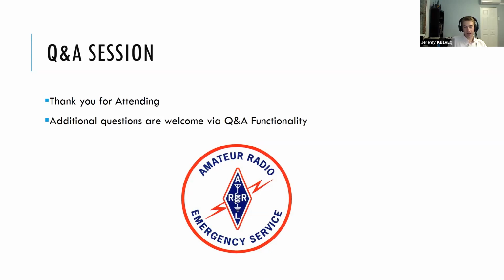It's one of those things, and it's obvious I'm an engineer when I say it, right? But efficiency is one of the things you pay for. So a quick and dirty inverter or UPS has a lower level of efficiency. Generally speaking, I don't think we're in the case where stuff is below 50 or 60 percent anymore. Switching electronics are generally efficient. We're in the 70 percent range and up. But 90 percent versus 95, that's your expensive UPSs, your expensive inverters, things like that. So definitely if you're looking to purchase one, it's a valid question to ask and to look into, but it is going to vary across the market.